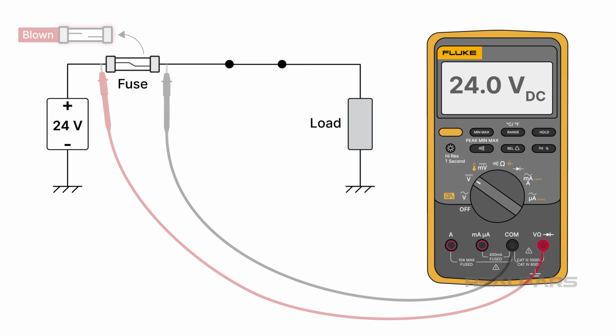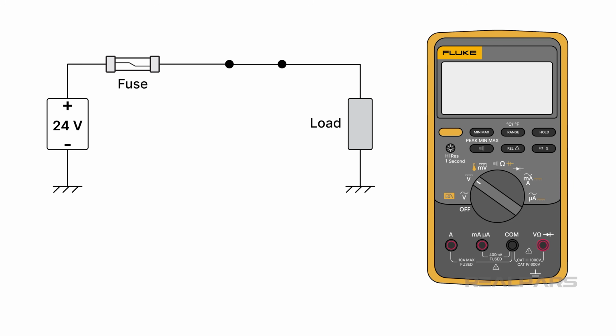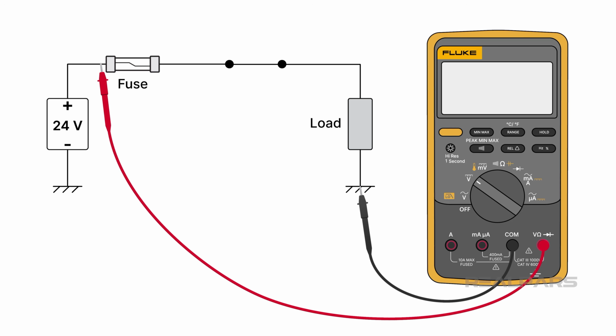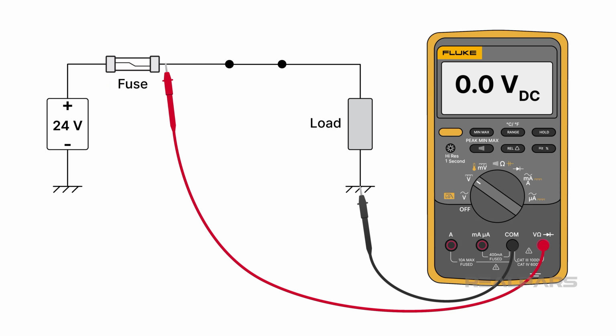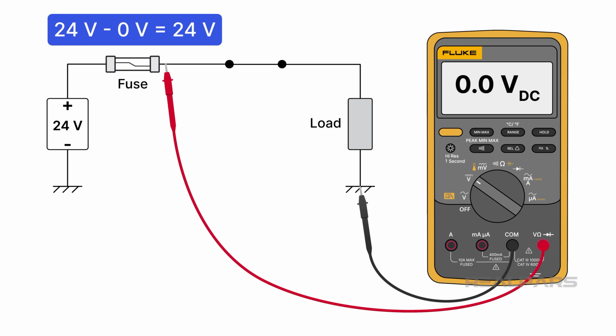Of course not. Instead of measuring across components using both hands, seasoned troubleshooters secure the voltmeter's black lead to common and use the red lead to probe selected points. Let's test the same fuse. The voltage from the fuse line side to common is 24 volts, and 0 volts to common on the load side. If you subtract the two measured voltages, you've mathematically derived the 24-volt drop across the fuse.